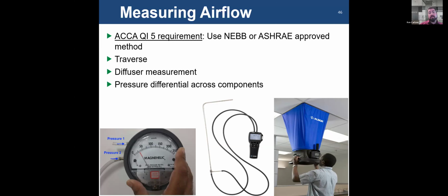Sometimes it's referred to as a hood. It directly measures the amount of airflow coming out of a diffuser. Right, that's your primary method. You can do a traverse in ductwork, right? Basically, you take an average of air velocity within that ductwork. There are charts to tell you what your distances should be and where you should take your measurements.